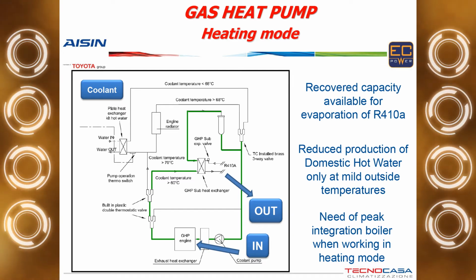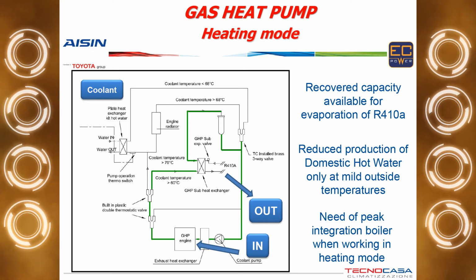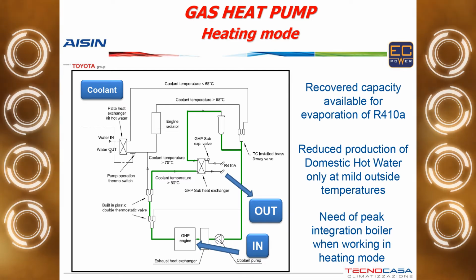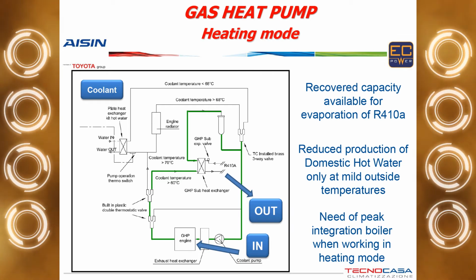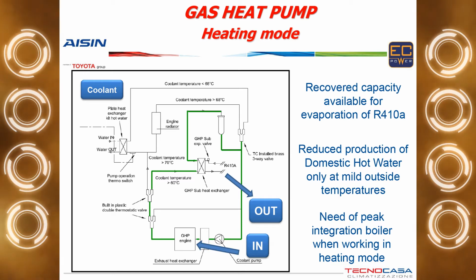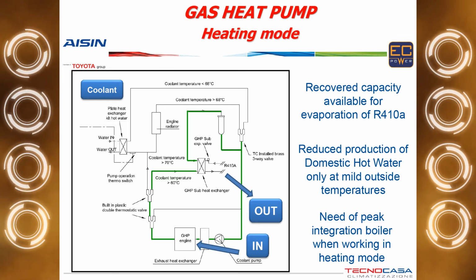troubles to the compressors. This has a positive effect also on the defrost cycles, because the local temperature of the fins of the coil is not very different from the outside temperature. And so when we are in those critical conditions around 0 degrees where ice starts to stack on the coil of a heat pump, the gas-driven heat pump is not affected by this problem. You have to think that just behind the coil of the refrigerant gas, we also have the engine radiator, which is warm. So usually when it's a very, very hard working conditions, you can see some stripes of ice on the heat exchanger. You will never see a stack of ice on the heat exchanger of the gas-driven heat pump.